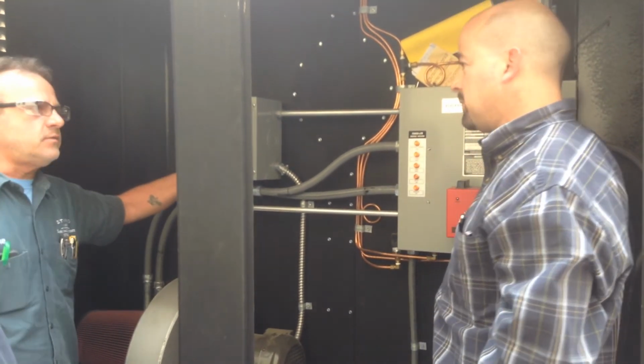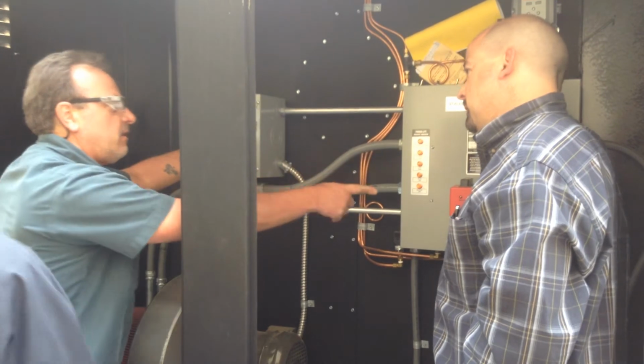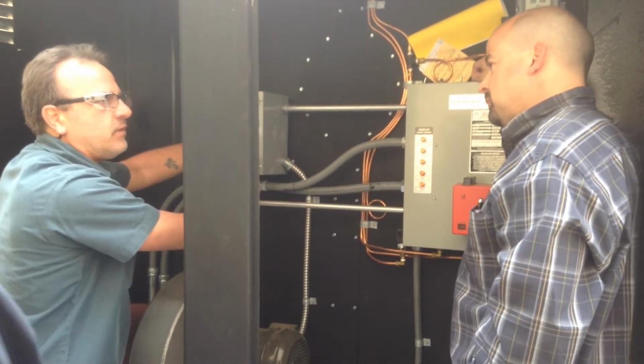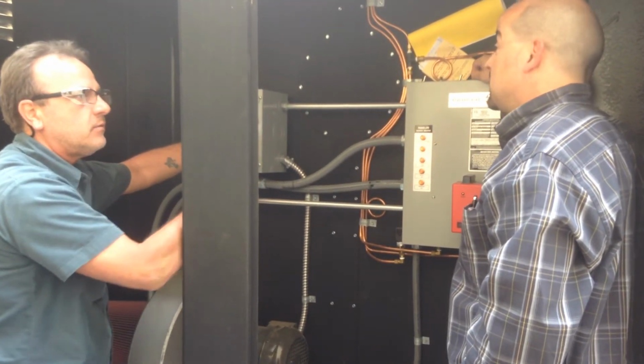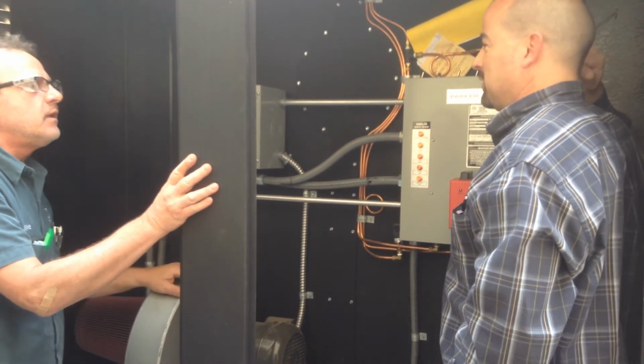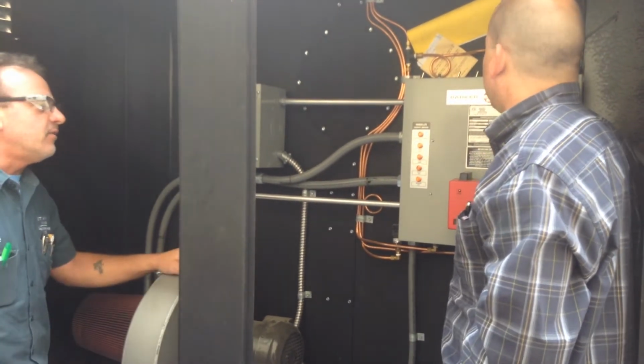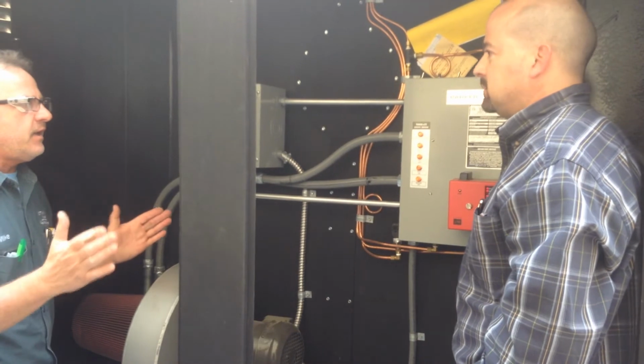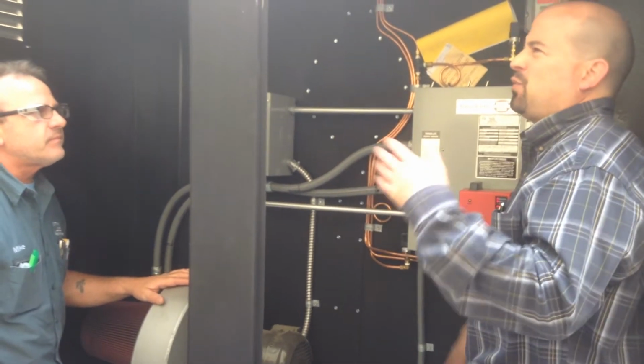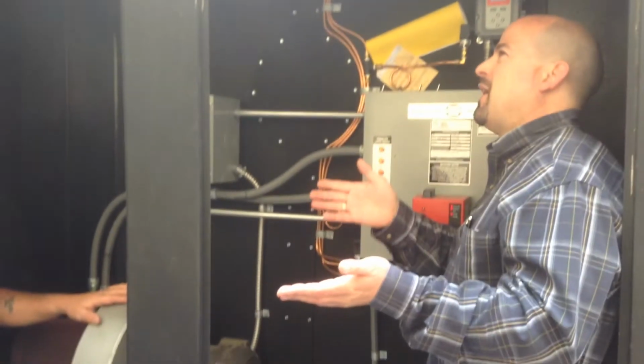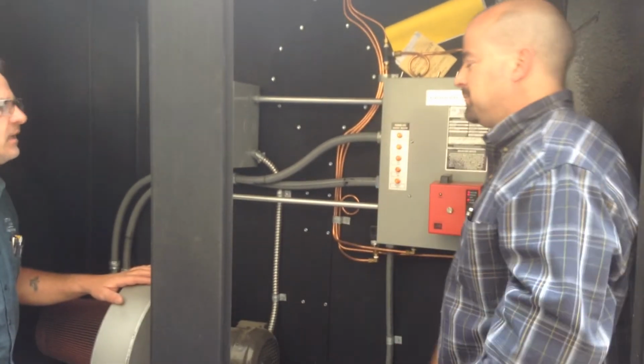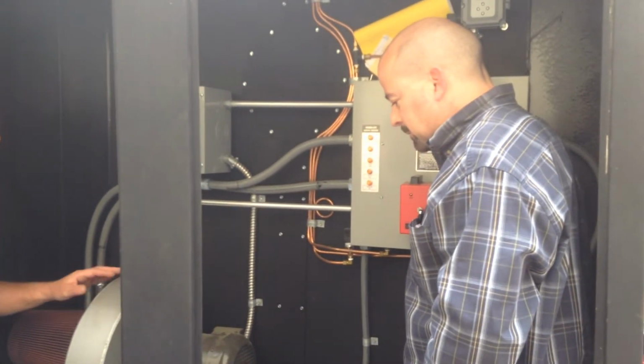So it really only has the high and low. If it's high or low fire, I'm only going to see two different readings here. Either I'm at low or high, and you'll see anything in between when I release it to modulation. I got you. Okay, I see. Anything from low to high. Usually it's like 20 to 45, and then anything in there. Gotcha.